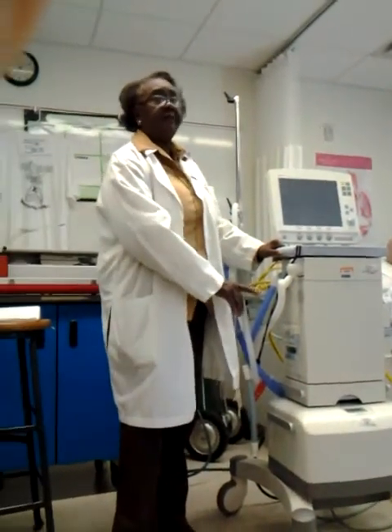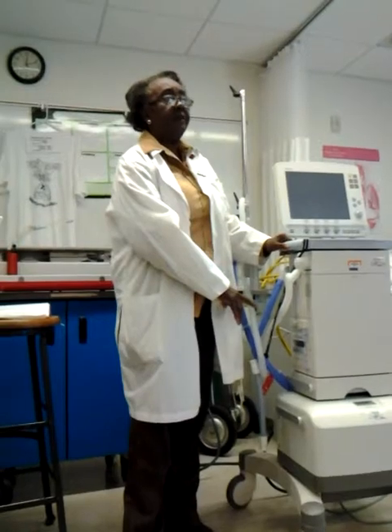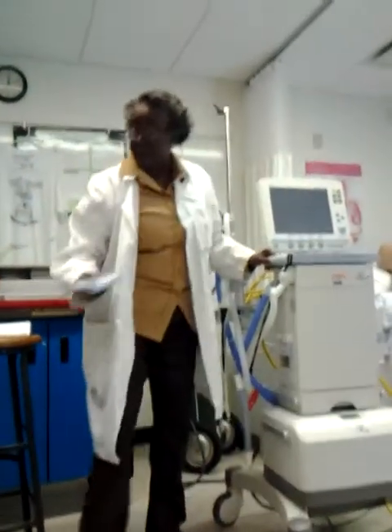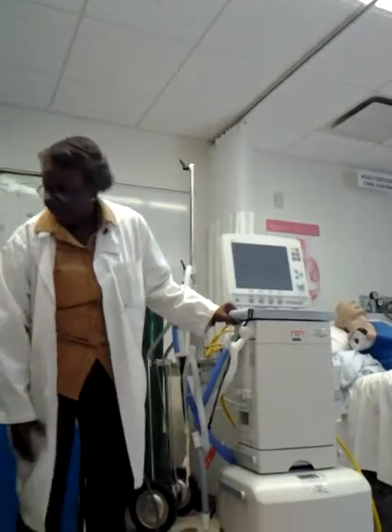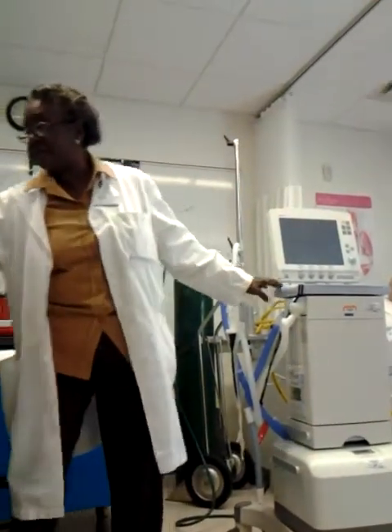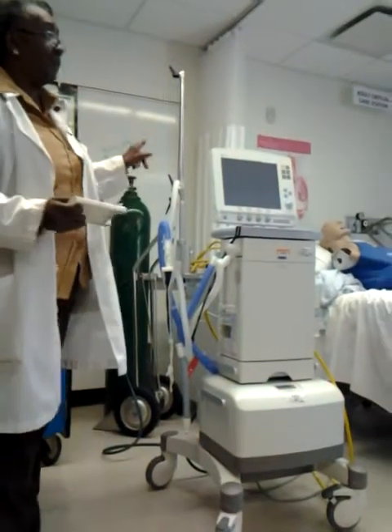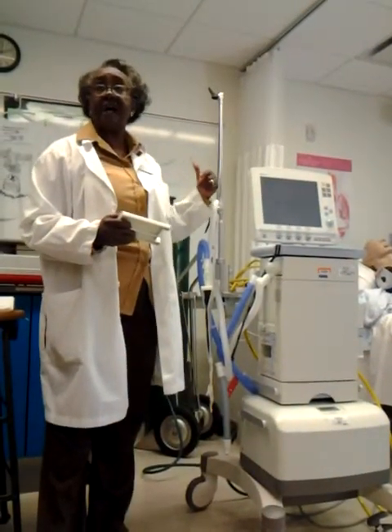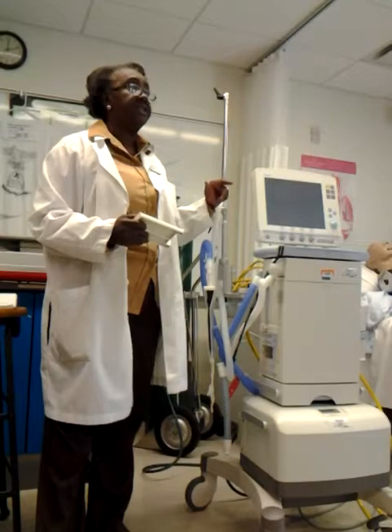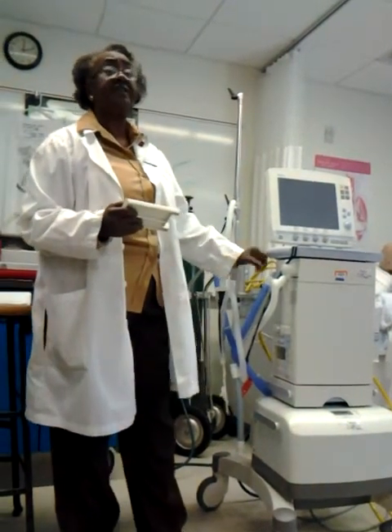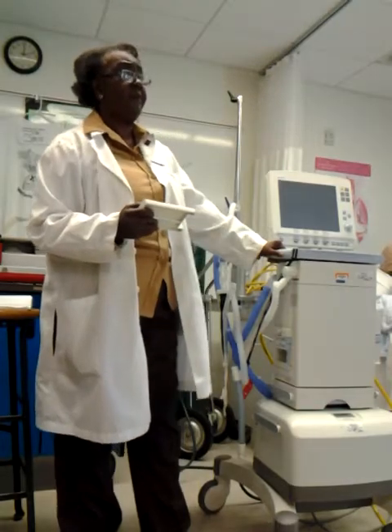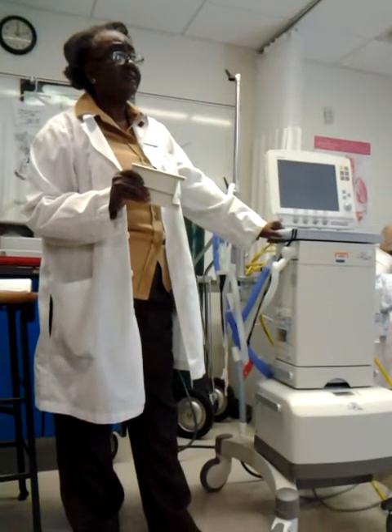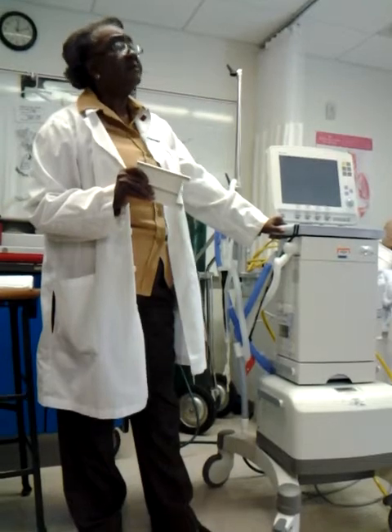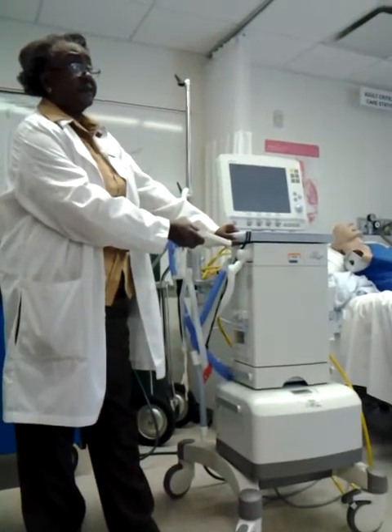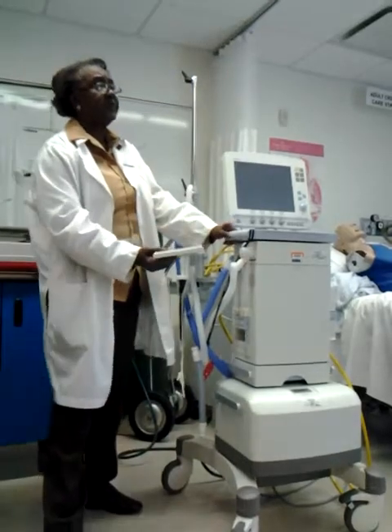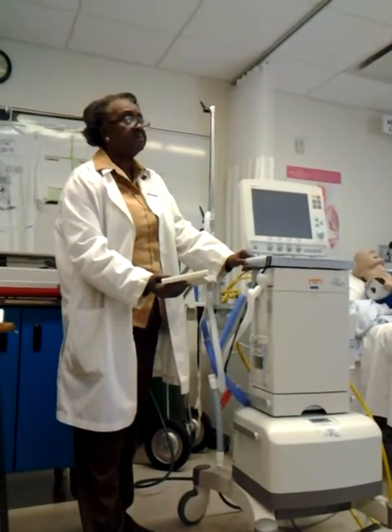So if you have to transport somebody, you have your battery packs that you can use. Do those batteries recharge when you plug back into the wall? Yes. When the ventilator is plugged in, that's why I try to keep both of these ventilators plugged in at all times, because the batteries are being charged as long as it's plugged in. And will they develop a memory? No. And will the backup turn on the compressor and humidifier? No, it just runs the machine itself. The 840 won't run the compressor or the humidifier either. It'll just run the ventilator. Same thing.